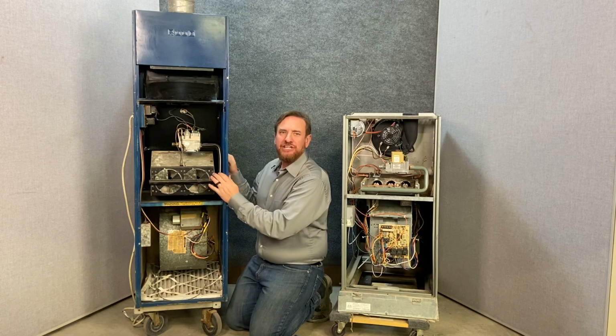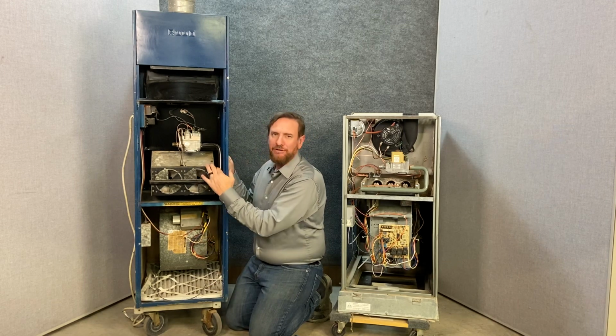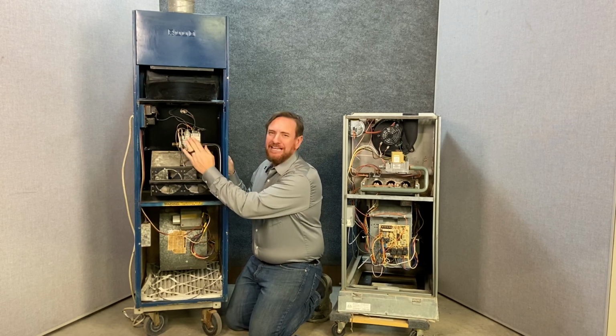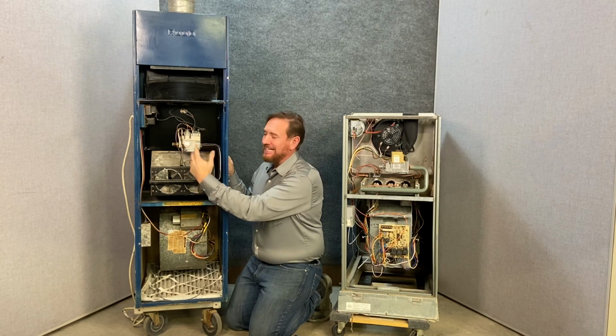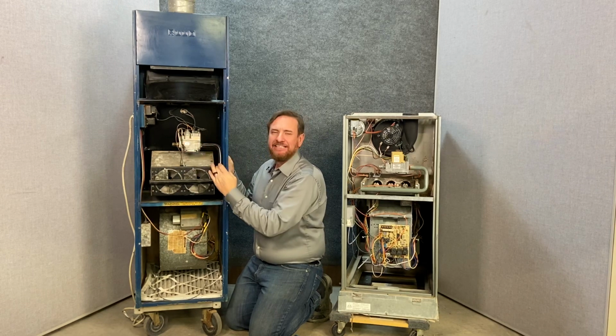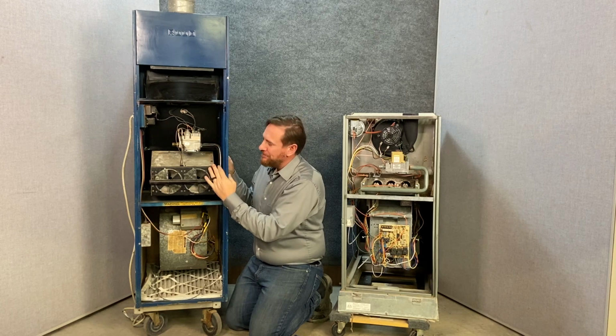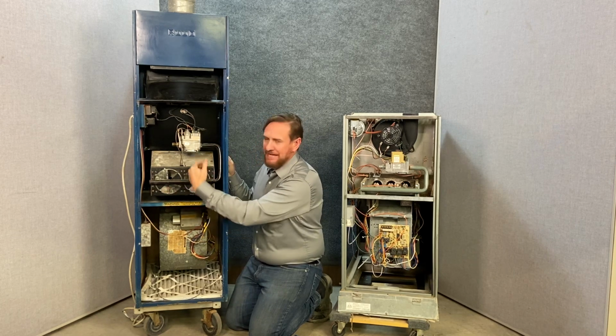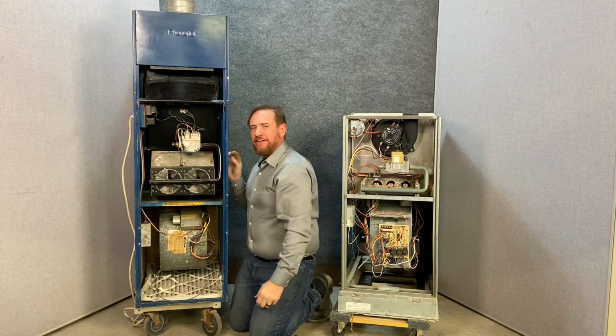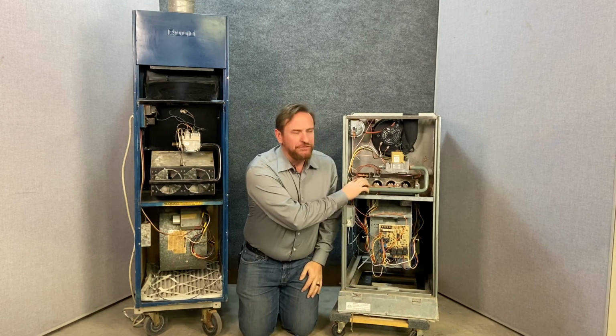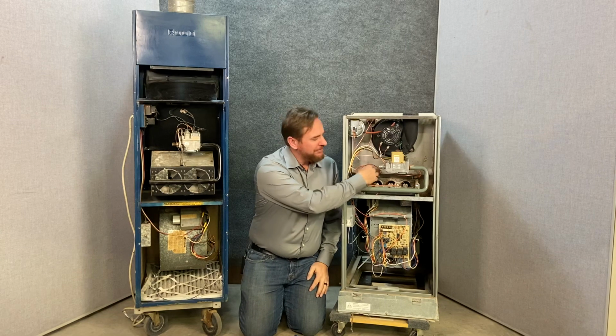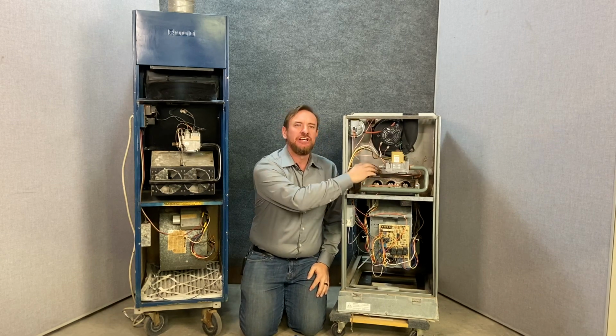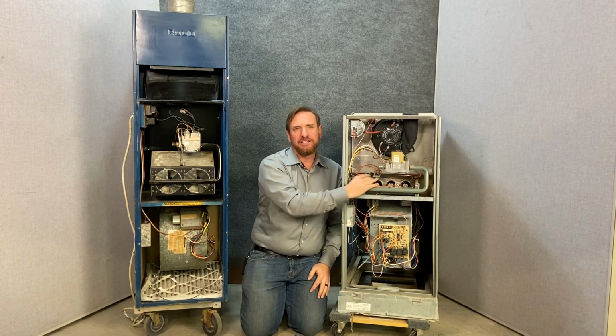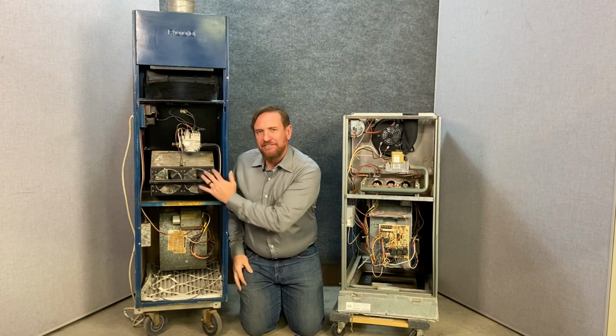But sometimes you had an issue where the flame would blow out, the thermocouple would keep this valve open too long and gas would build up, and then when it finally ignited from a spark, it would become a miniature little explosion. So that was an issue. Also, there was no safety to keep that gas from rolling back out. This furnace has flame rollout switches. They're extra safety devices. So if the flame were to come out of this heat exchanger, this shuts the whole system down quickly and efficiently. This older one has none of those systems.